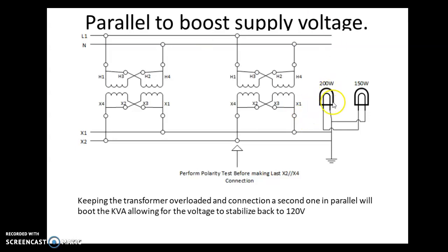By connecting the same 2 lamps, 350 watts or higher, and having these transformers put in parallel, we've increased the amount of available kVA rating for the transformer bank. We still have the isolation that's required for a control transformer circuit, but we will now have enough voltage to power both loads. When I mentioned the paralleling of transformers, I also mentioned doing a polarity test.